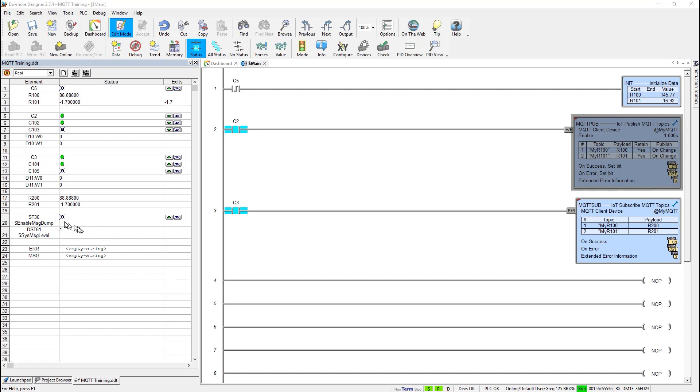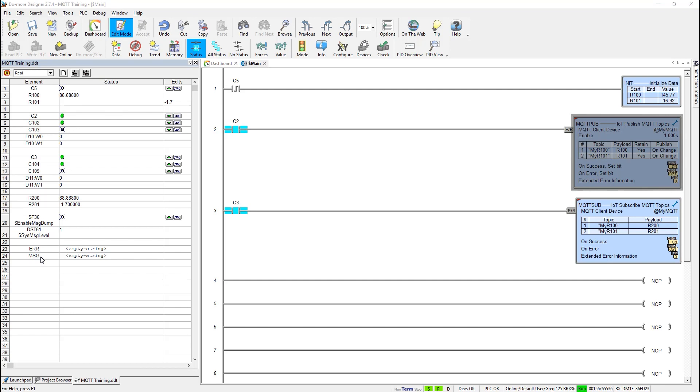And also it's associated with this value, DST61, which is the system message level. By default, this is set to 1. And it means that when this is turned on, then this 1 here means only send the system error messages to DoMore Logger. When I change this value to 2, then it means send the error message and the system message. Send both of these to the logger. And when I have it set to 0, then of course it won't send anything.